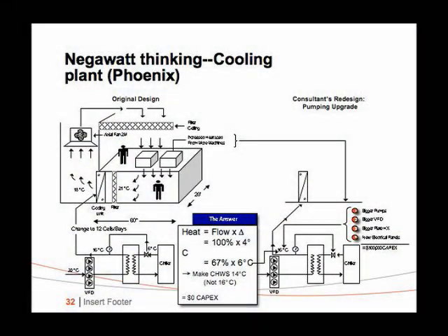And if you think out of the box a little bit, these dry coils are run with 16 degrees chilled water. And we get the 16 by going through a heat exchanger from the chiller. So the automatic reaction for many of us is, it's 16 degrees, I need more flow, I know where I can buy pipes and pumps and so on. The other way of thinking is, how can I do more with less? So you go back and you ask the Toyota production system, the five whys.